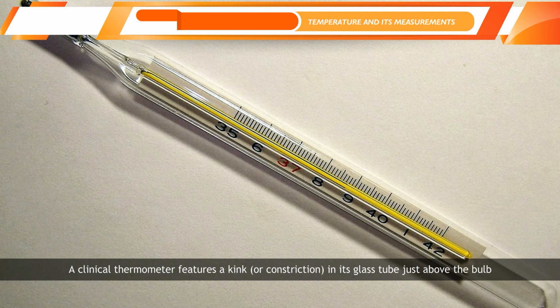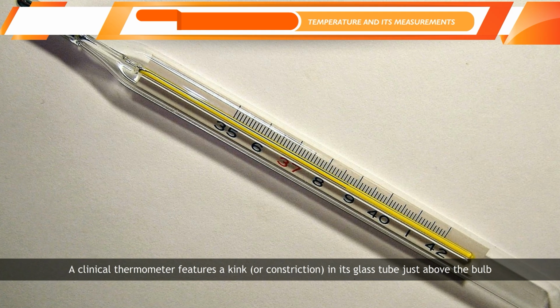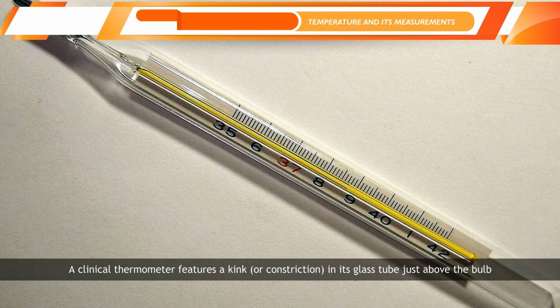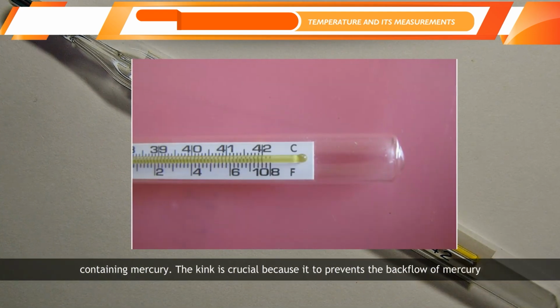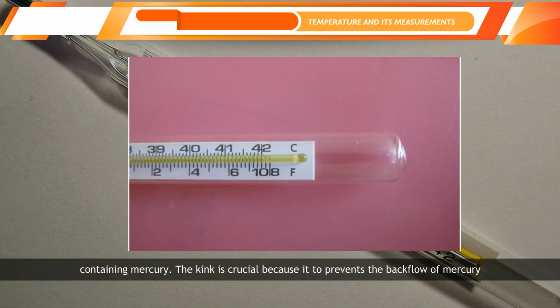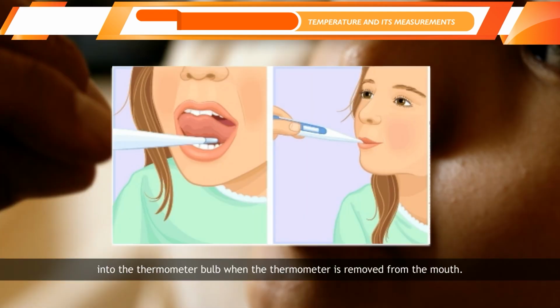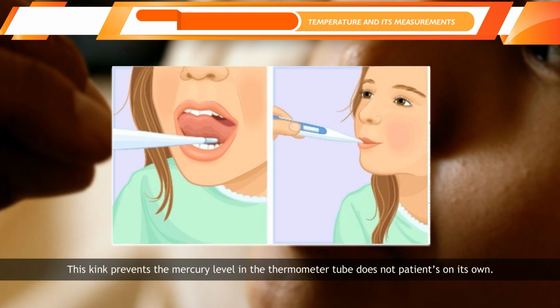2. A clinical thermometer features a kink or constriction in its glass tube just above the bulb containing mercury. The kink is crucial because it prevents the backflow of mercury into the thermometer bulb when the thermometer is removed from the mouth. This kink prevents the mercury level in the thermometer tube from falling on its own.